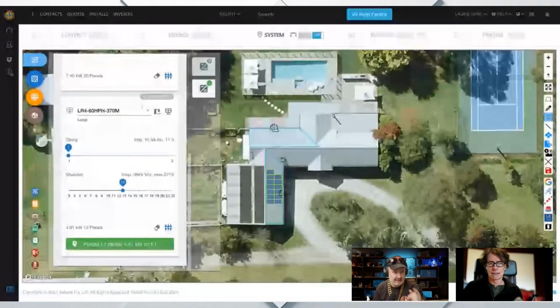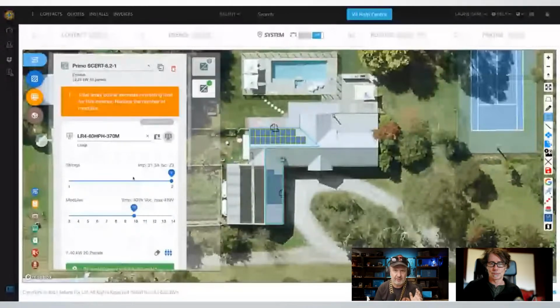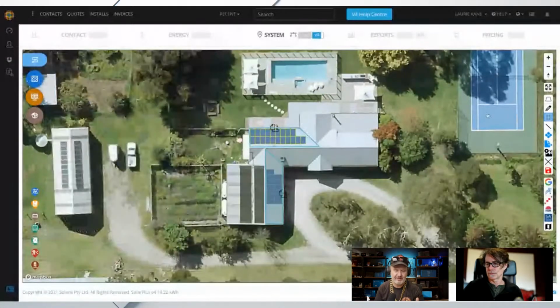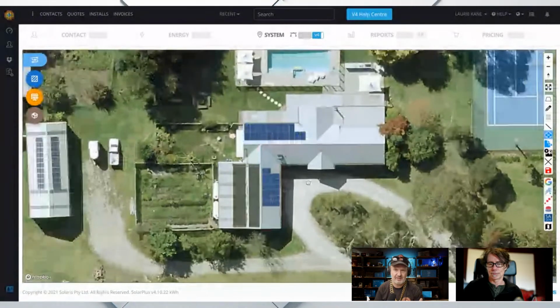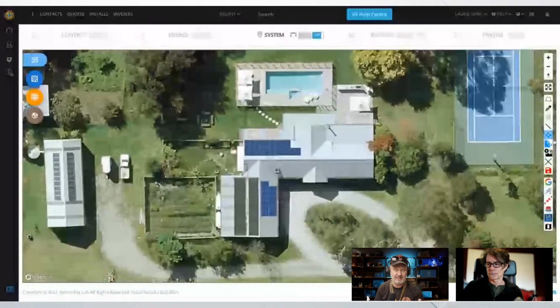Actually, Laurie, can I once again interrupt while you're doing that? I just want to pick up on your east-facing array comment. With off-grid, you'll often be at your low ebb, certainly in wintertime, first thing in the morning, and you really want to get some charge into the battery system or to supply the loads. So that east-facing array is kind of your kickstarter for the day.